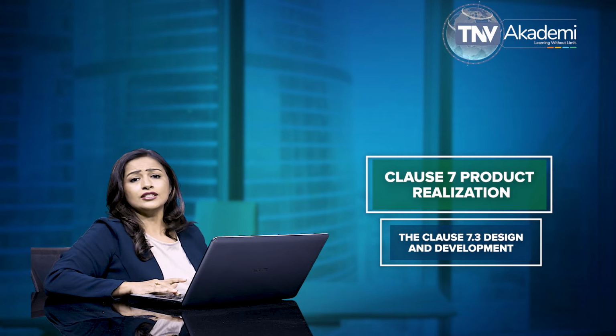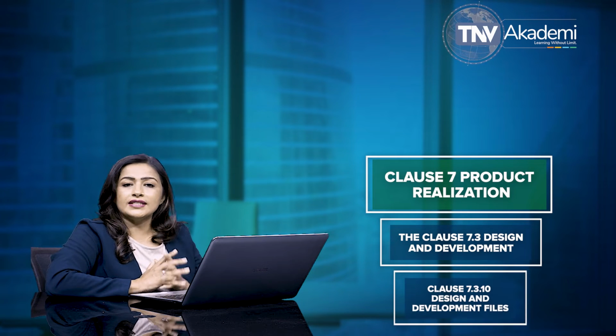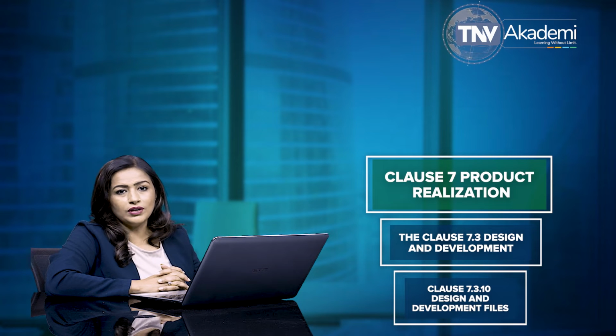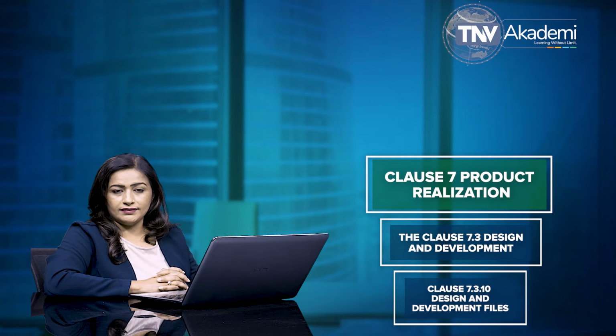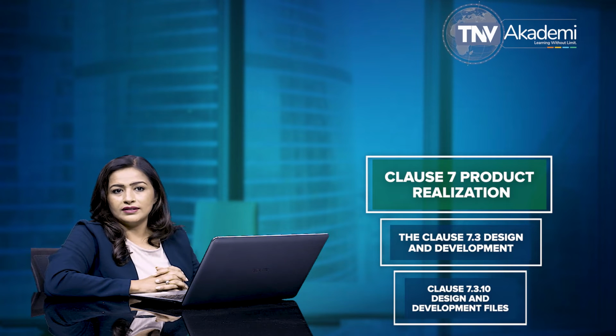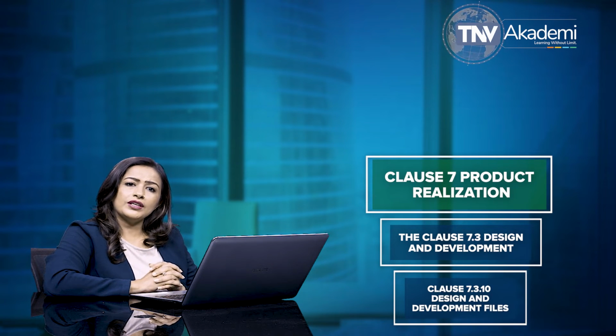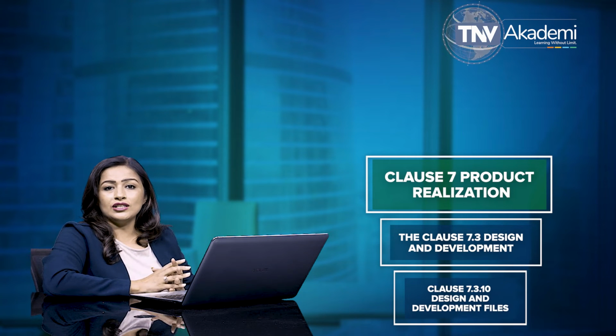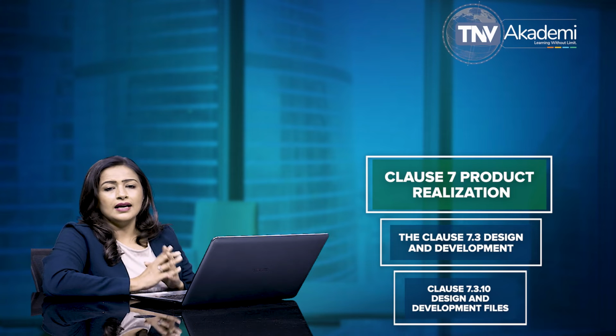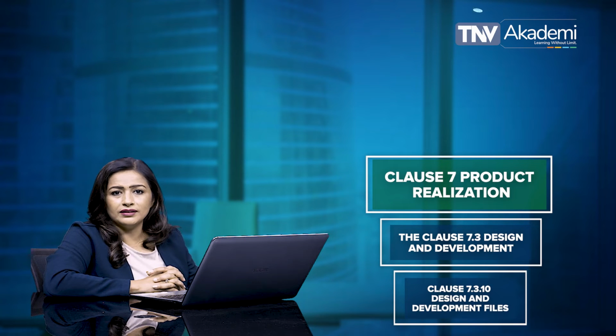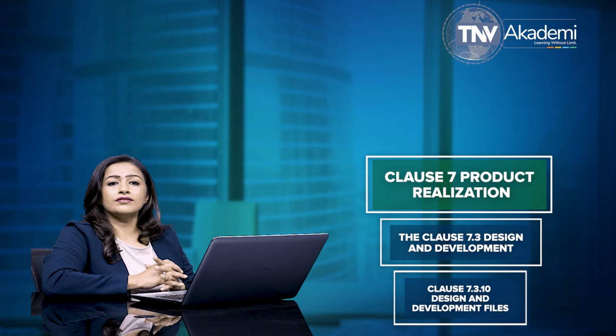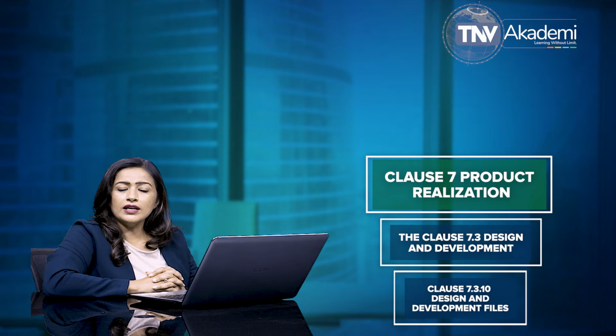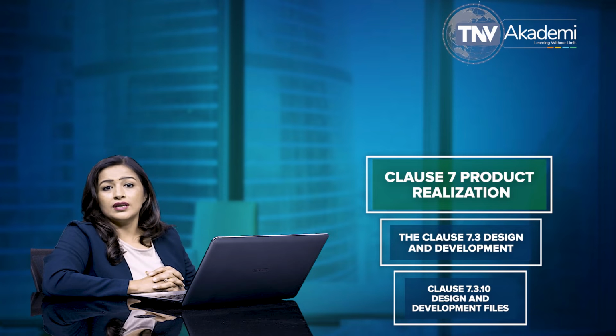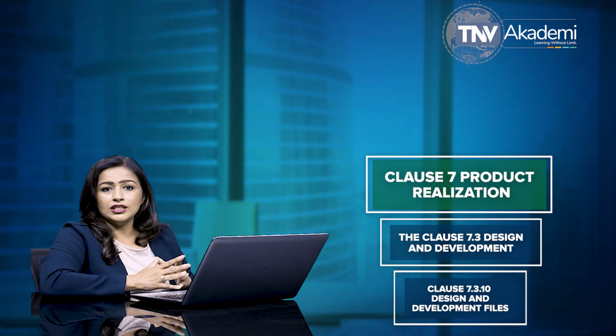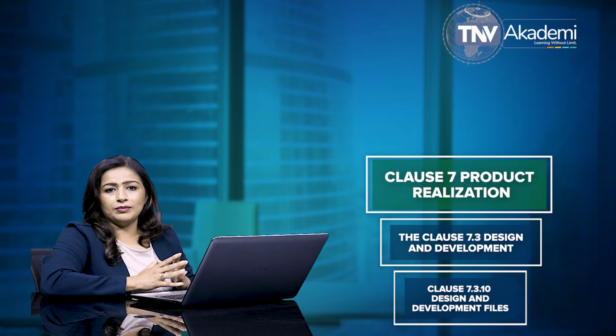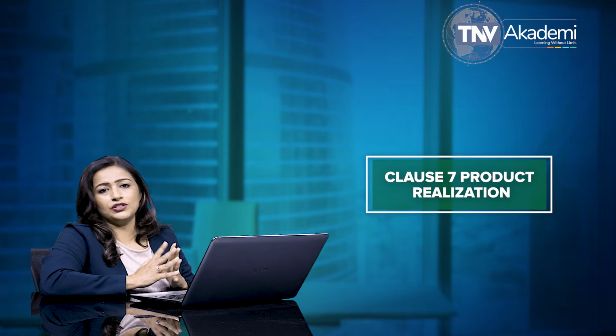Now, let's talk about subclause 7.3.10 of ISO 13485:2016, that is, Design and Development Files. Subclause 7.3.10 specifies that the organization is required to maintain a design and development file for each medical device type or medical device family. This file is required to include or reference records generated to demonstrate conformity to the requirements for design and development and records for design and development changes.